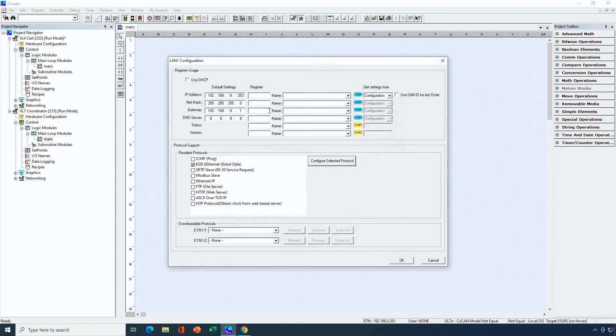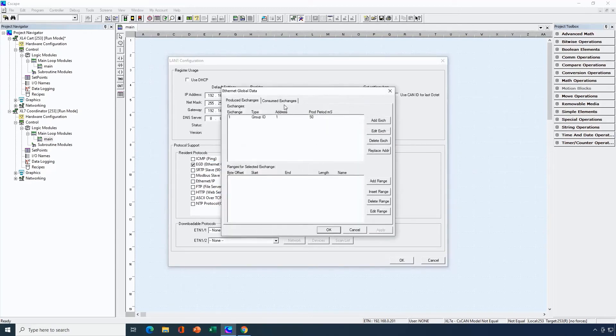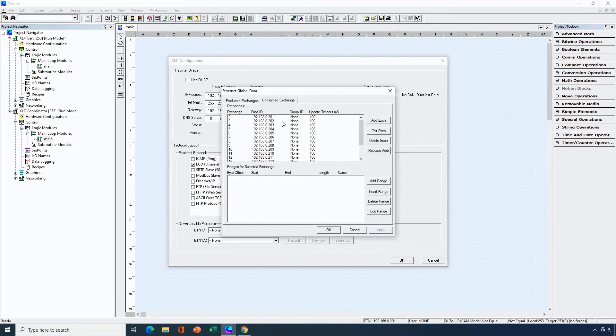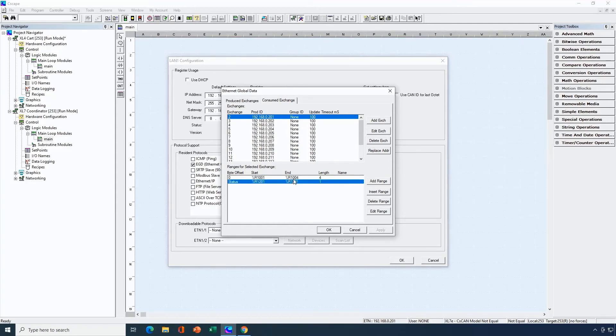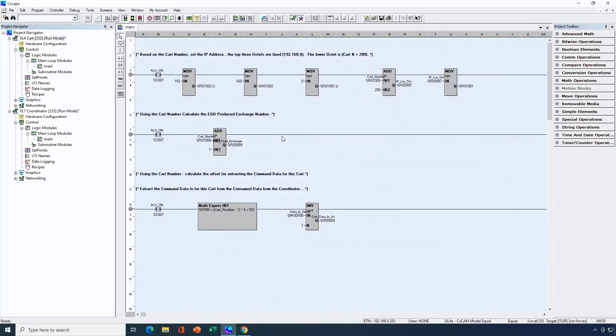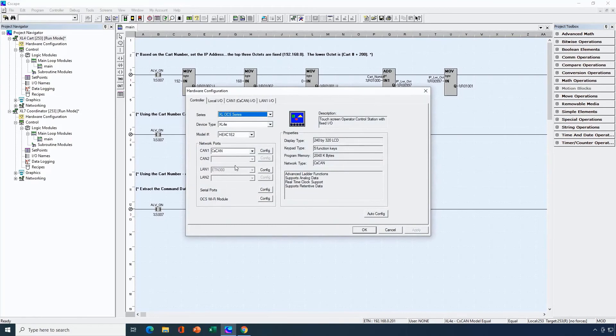Now let's look at the consumed side at the coordinator level. This is the data that's coming in from the cart XL4s. We have 16 exchanges configured, one per cart. Here are the unique exchange numbers from the ID of the cart that's sending the information. There's no group ID affiliated with it and we've set a timeout for receiving the data at 100 milliseconds. The data coming in is just 4 words from each cart and the status information from the carts. Now let's look at the cart side. I want a single logic program that's used by all the carts so we don't have 16 different programs to maintain. So first let's start at the EGD configuration — I'll go into lan1 config.